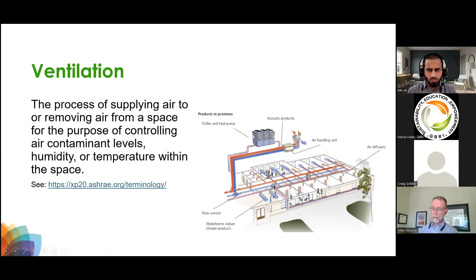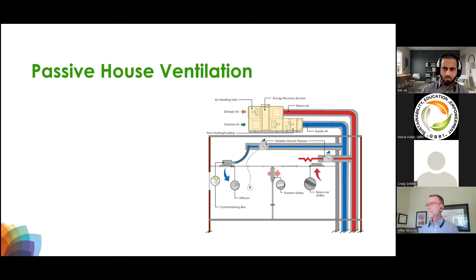In a passive house, we're also trying to do some other tricks that I won't focus too much on here today, but we want to provide that fresh air in a way that uses as little energy as possible. So the typical path of air on a larger project, this could be a school, would be through a supply air ductwork that branches off and then goes into an occupied space. And the air flows to a corridor or a place that's less critical without ducting. Anytime you reduce the amount of ducting, you get to save energy, because energy by the fans and the air handler is consumed generating pressure that's enough to blow the air downstream. You can also do some post-heating and post-cooling.